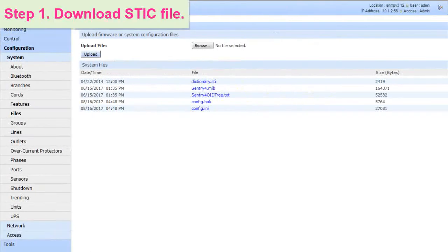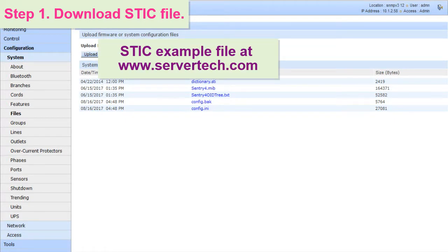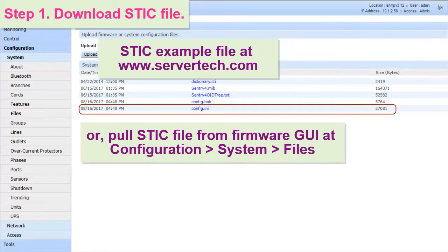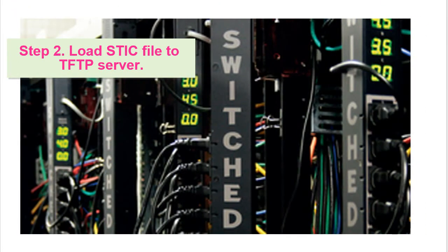Let's zoom in on how ZTP works. Step 1: Download the STIC configuration example file, or pull the file from an existing deployed PDU. Determine your PDU configuration and edit the STIC file accordingly. Step 2: Load the STIC file onto the TFTP server that all the ZTP capable PDUs can reach.